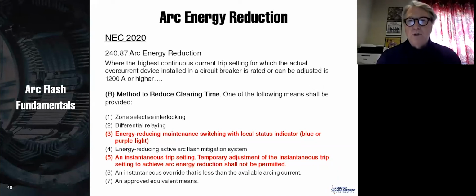You are still subject to this interpretation because it could be adjusted to 1,200 amps or higher. What if you have a 1,200 amp frame breaker, but it's got a trip unit, adjustable or not, that does not allow you to set that breaker higher than 1,000 amps? Then you would not be subject to this. So it depends upon the trip device in there.